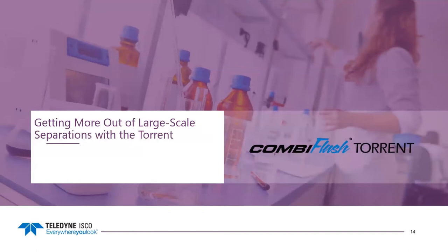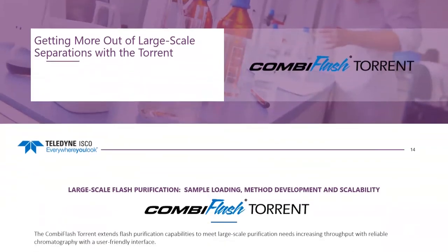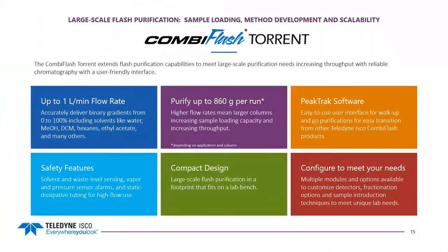The CombiFlash Torrent extends flash purification capabilities to meet large-scale purification needs, allowing increased throughput with reliable chromatography and a user-friendly interface. We can go up to 1 liter per minute flow rate, do binary gradients between A and B solvents, run from 0 to 100% with a variety of solvents in normal phase and reverse phase. We can purify up to 860 grams per run in some cases, dependent on application and column type. Higher flow rates allow use of larger columns, increasing sample loading capacity and throughput.